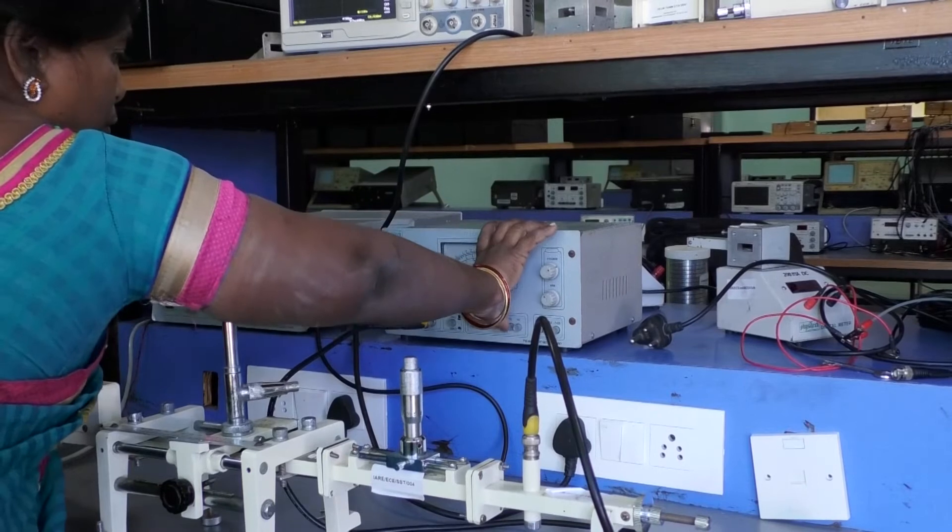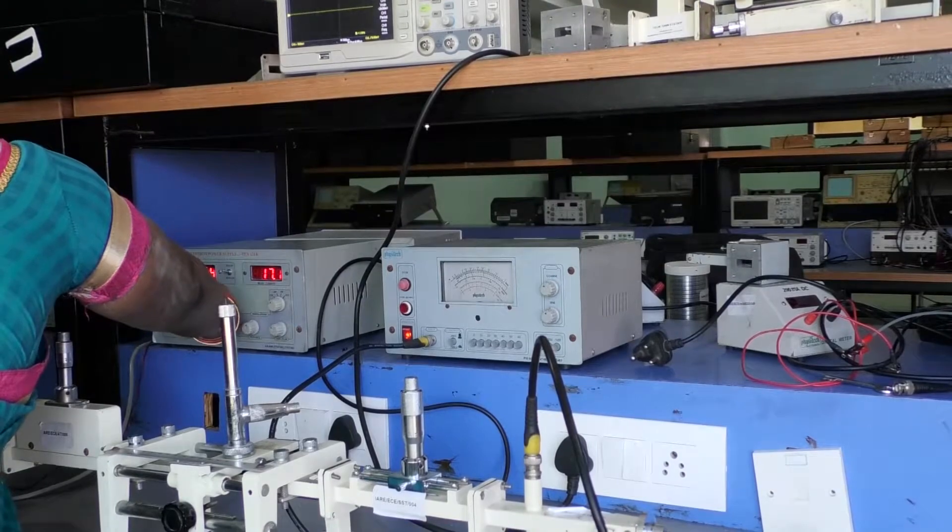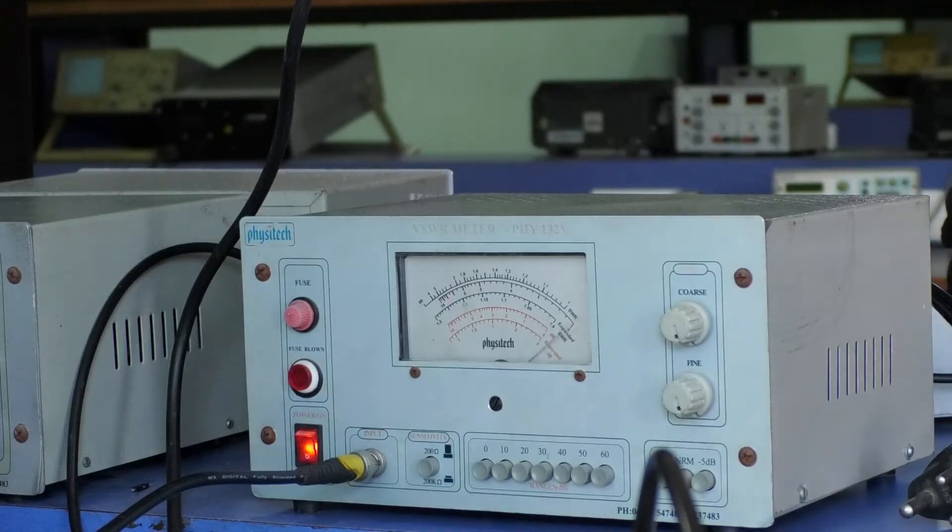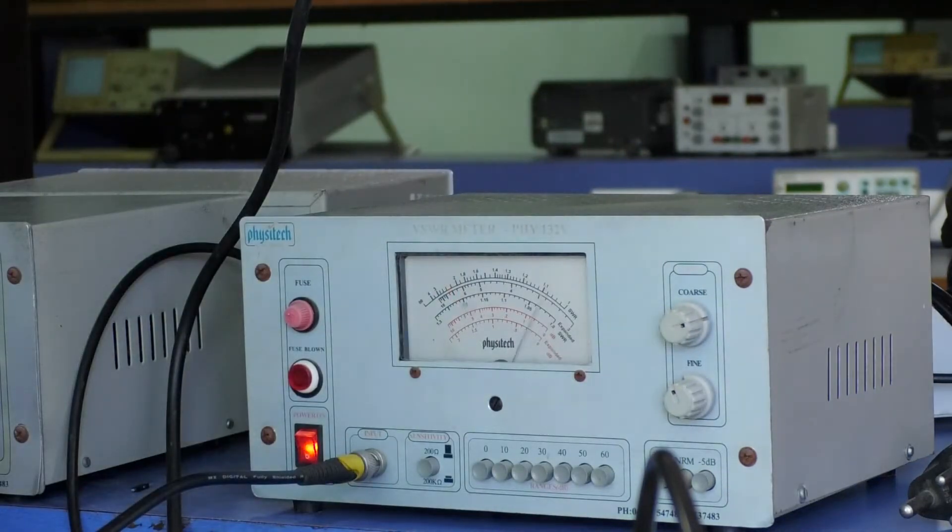We can vary the coarse structure or gain structure or repeller voltage. Now the VSWR is set to 1. Or we can also vary the variable attenuator position to set the VSWR reading as 1 on VSWR meter.